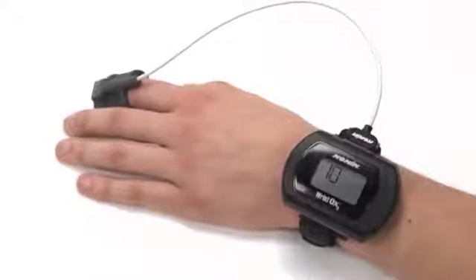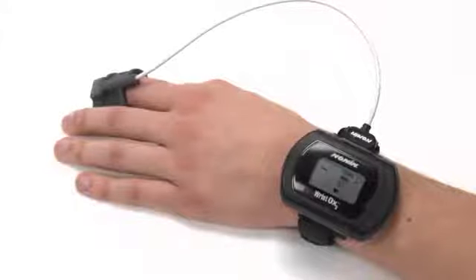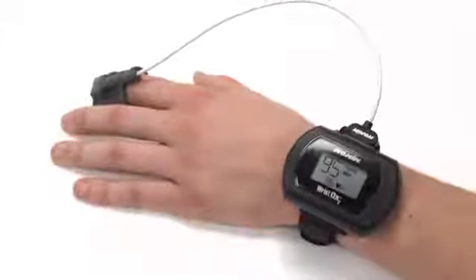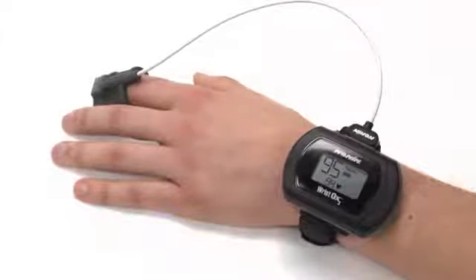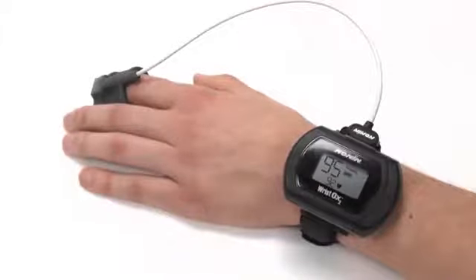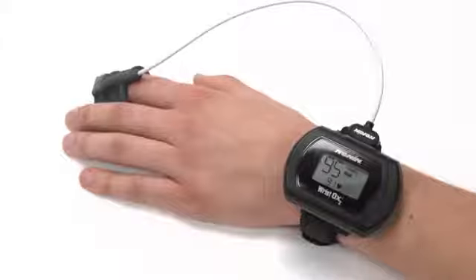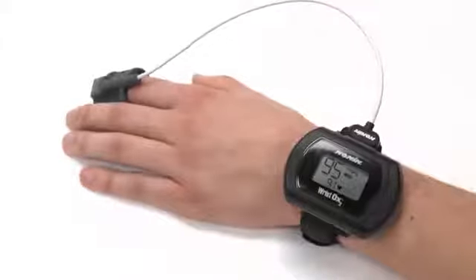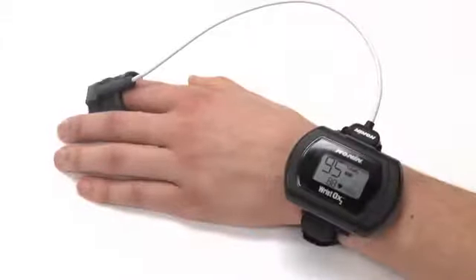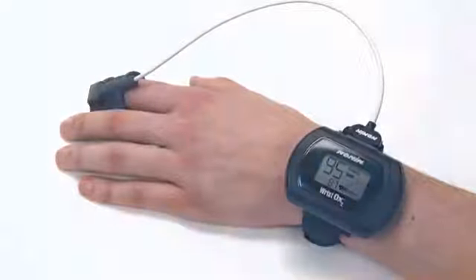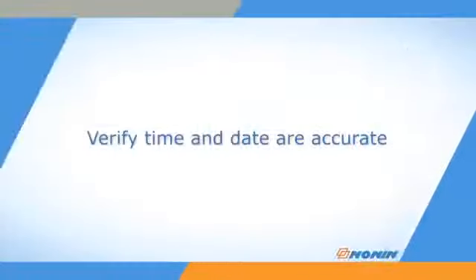If the activation switch is pressed in programmed mode, the oximeter immediately activates the Bluetooth radio and operates for 3 minutes. During this time, the oximeter takes and stores measurements. After 3 minutes, the oximeter returns to standby mode and will reactivate at the next programmed mode session. When using programmed mode, verify all time and date settings on the oximeter are accurate.